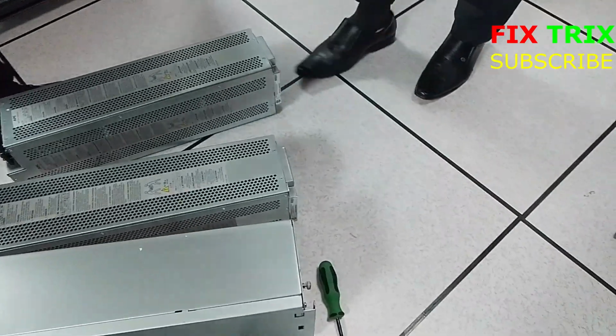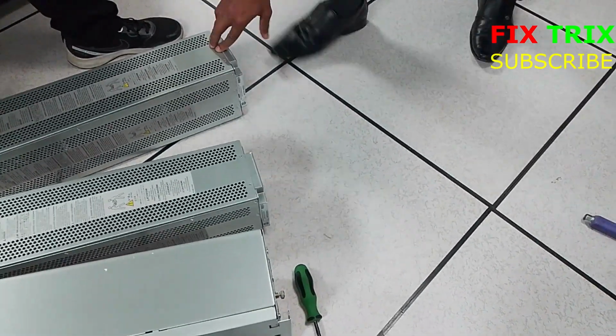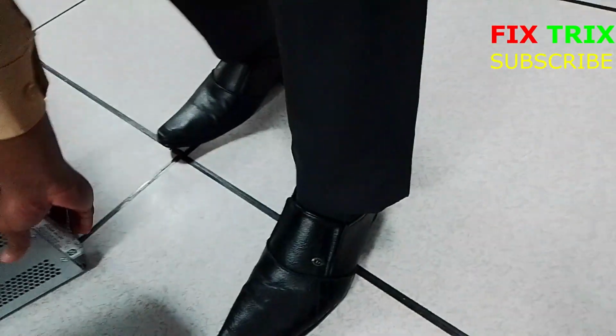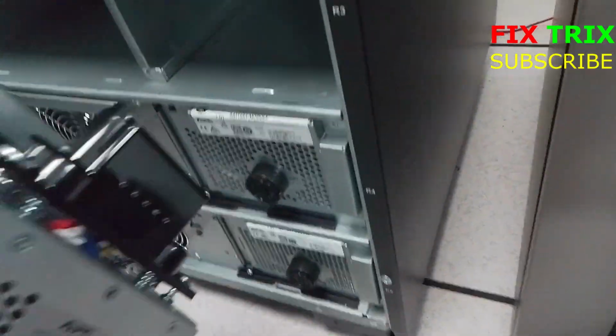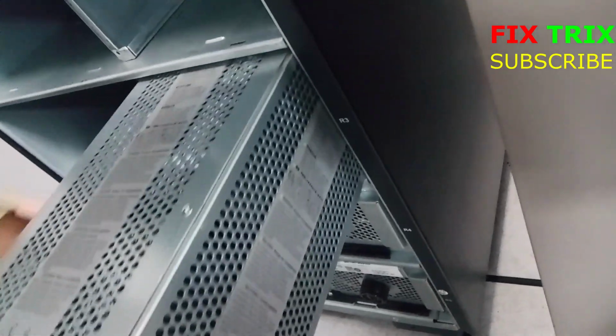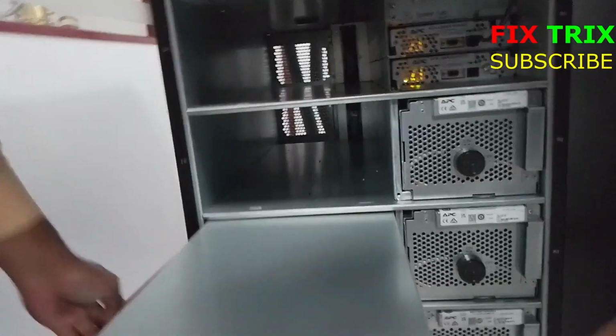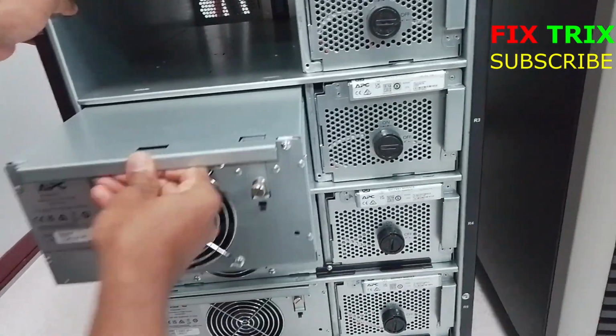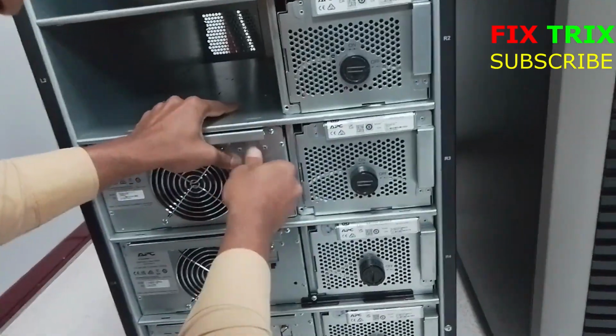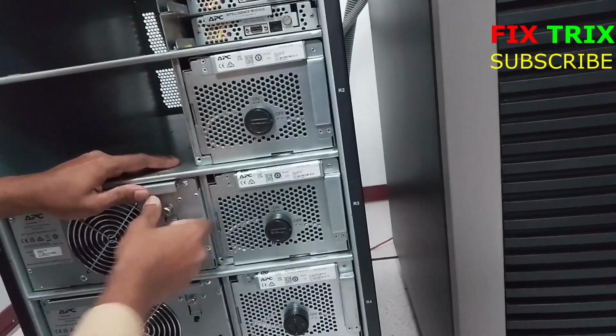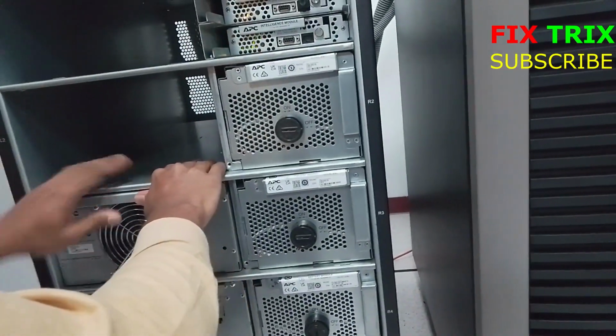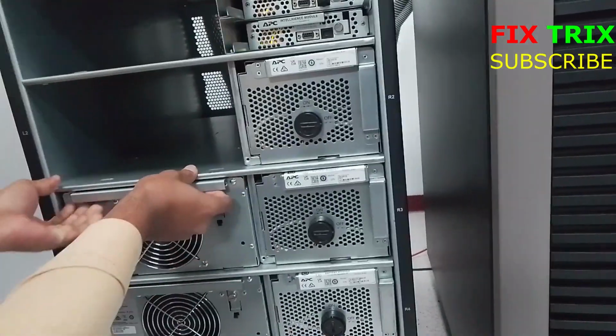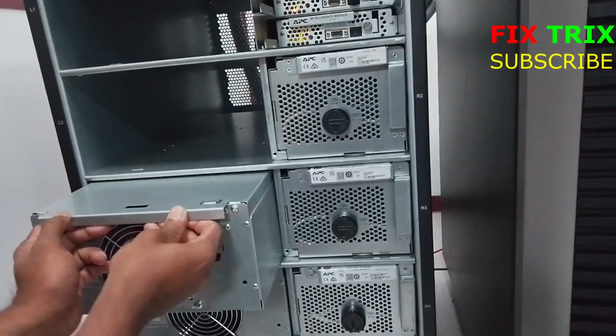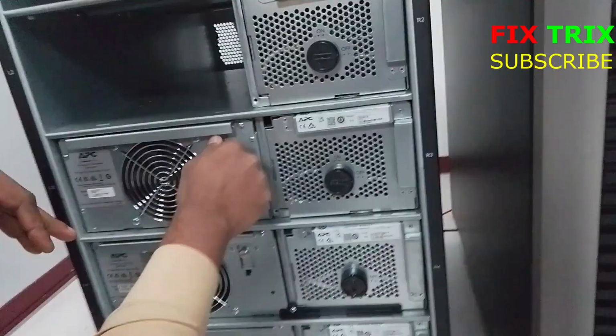Now we install all remaining power modules and battery modules. At this time the UPS is in maintenance bypass mode, so the load is powered directly from utility. This allows us to work on the UPS safely without disturbing the connected equipment. We take one power module and slide it slowly into the correct slot. We push the module inward until the front is fully seated and flush with the UPS. You will feel the safety catch lock. Then we tighten the retaining screw. We repeat this step for all remaining power modules and battery module.